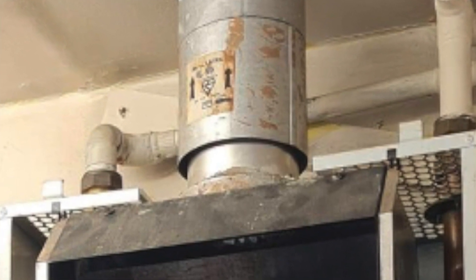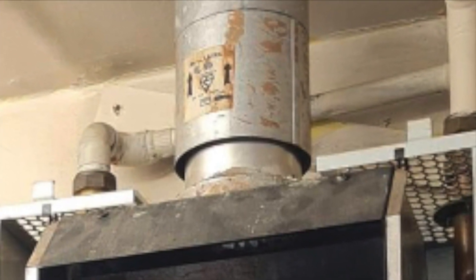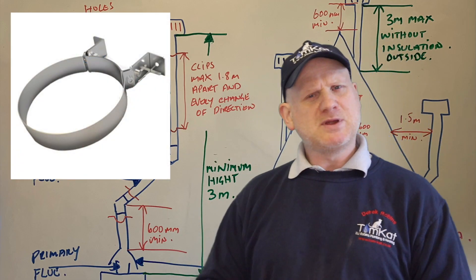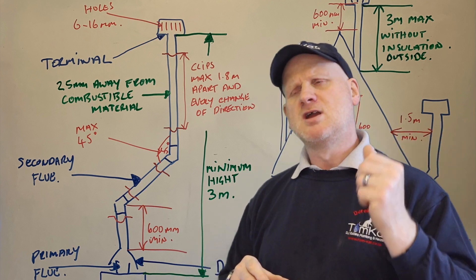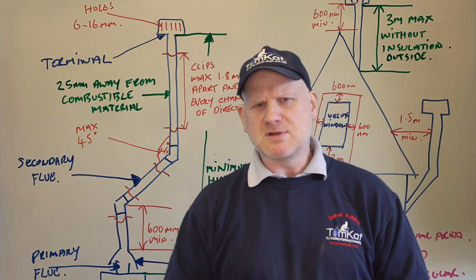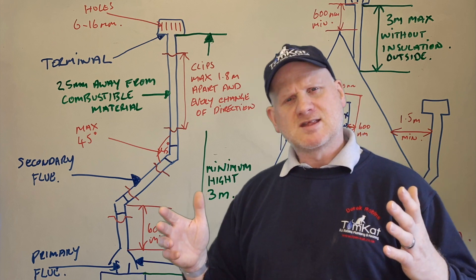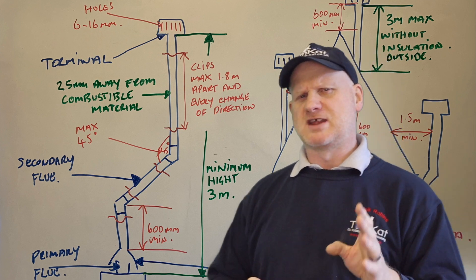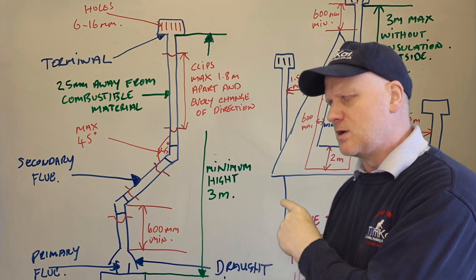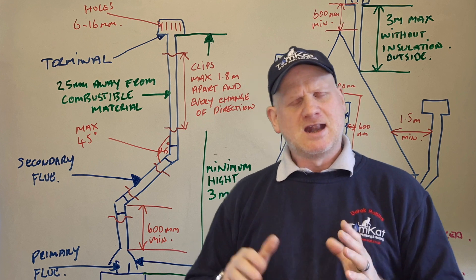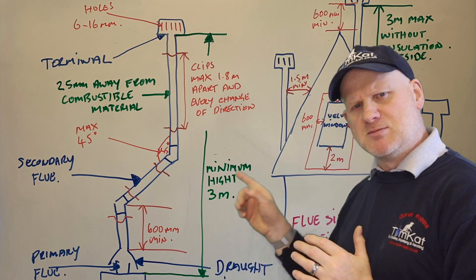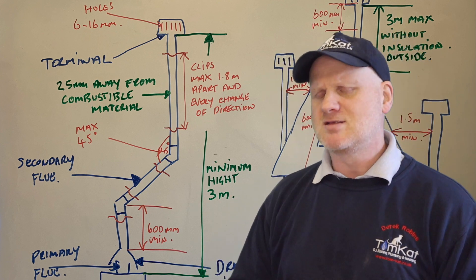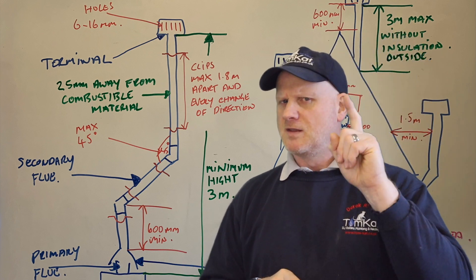You must follow the arrows on the flue system so you don't install it upside down. The maximum clipping distance is at every change of direction and no more than 1.8 meters apart — though many condensing boilers specify a maximum of one meter, so check manufacturer's instructions. The minimum height for an open flue appliance is three meters.